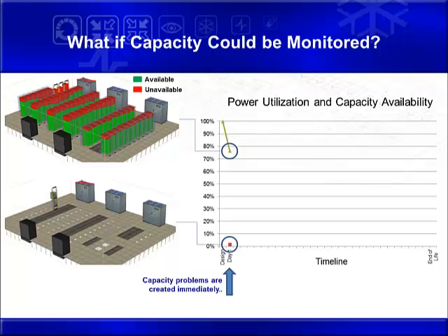This is typical, and this happens because the actual IT configuration differs from the design assumptions. These include things like cabinet geometry, IT unit size, airflow utilization, and placement in the cabinets. Again, this effect is real, but goes unseen today because data center capacity isn't being monitored.